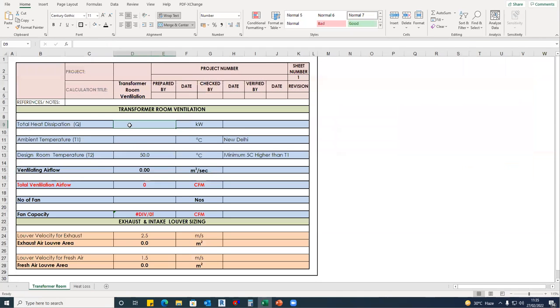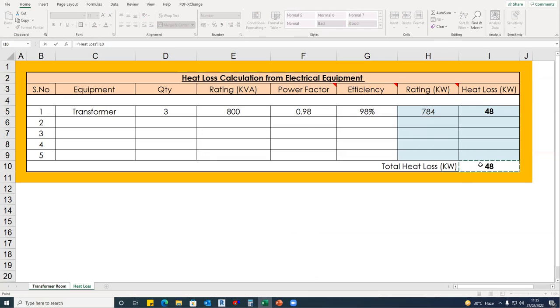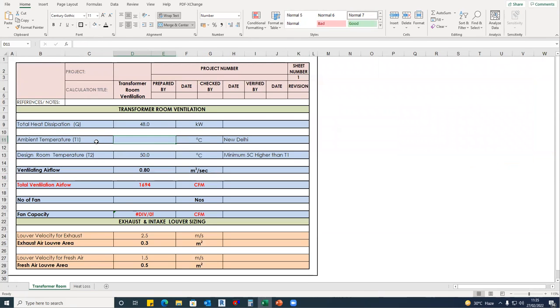Okay, so I'll use this 48 kilowatt, or you can link this 48. Okay, and next it is asking for the ambient temperature. So ambient temperature for New Delhi, I'll take, for example, 43 degrees Celsius. Okay, design room temperature should be minimum 5 degrees higher than T1. So T1 is the ambient temperature, and minimum it should be 5 degrees higher. But maximum, in the DG room, is 50 degrees Celsius. But in the case of a transformer, we cannot go beyond; the maximum allowable temperature is 55. This is for the transformer room and that is for the DG room. Okay. So design temperature, I'll take say 50 degrees Celsius. It is higher by more than 5 degrees temperature difference.